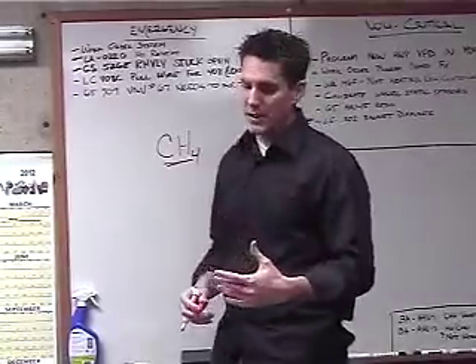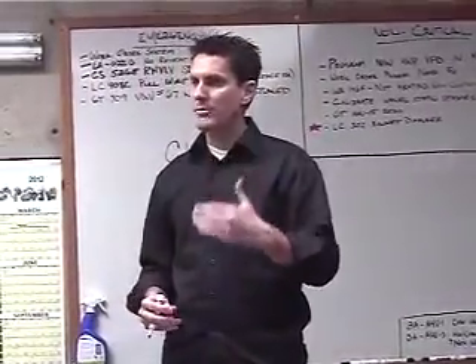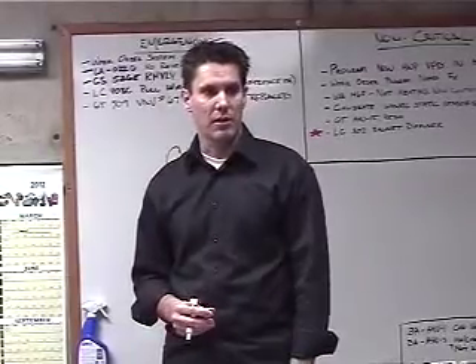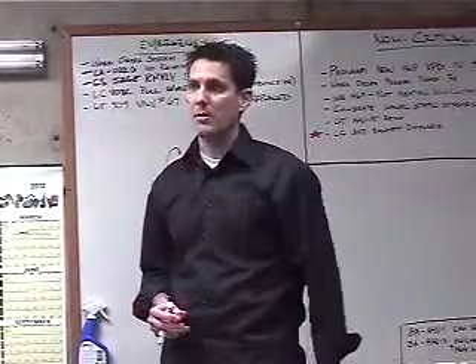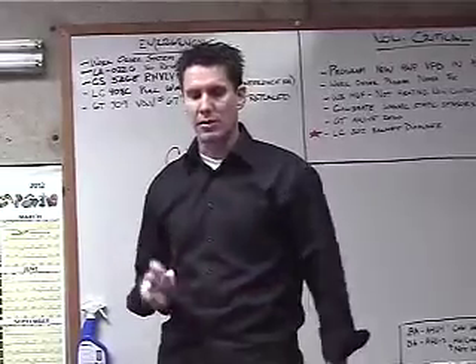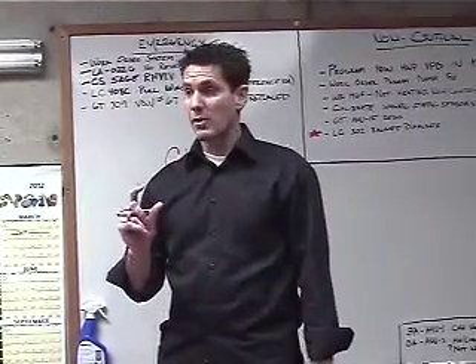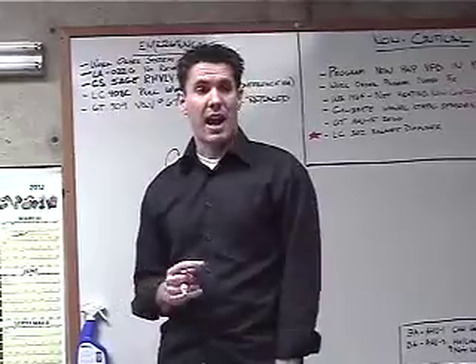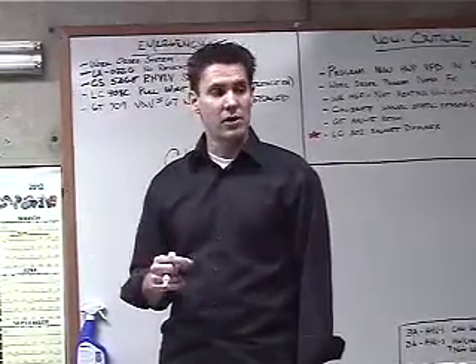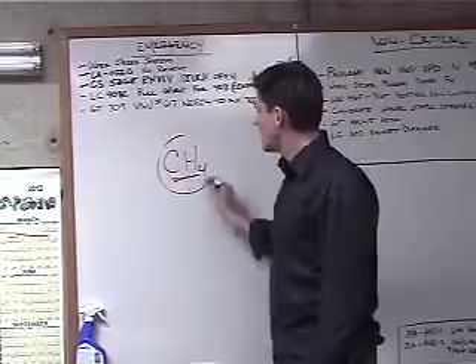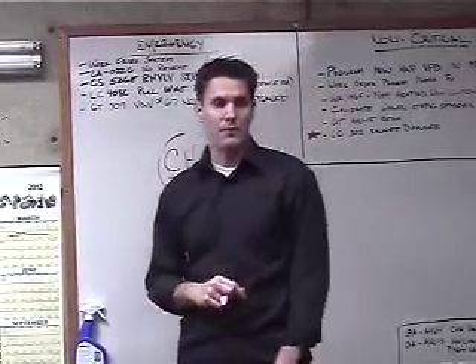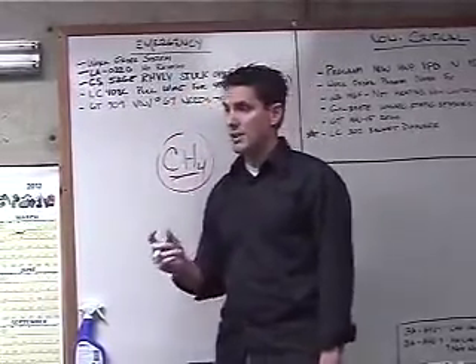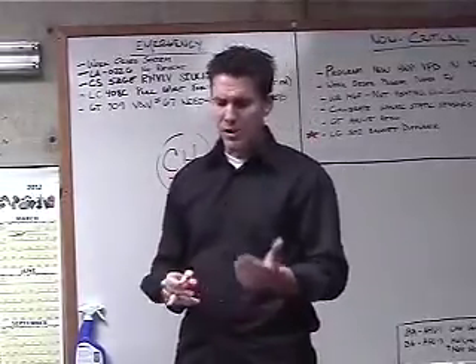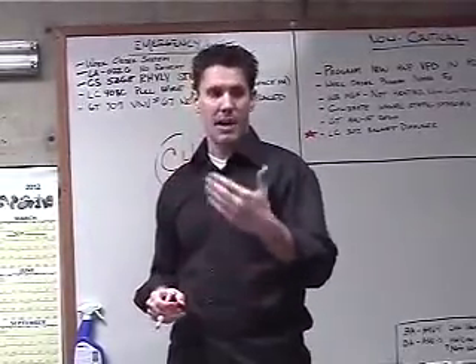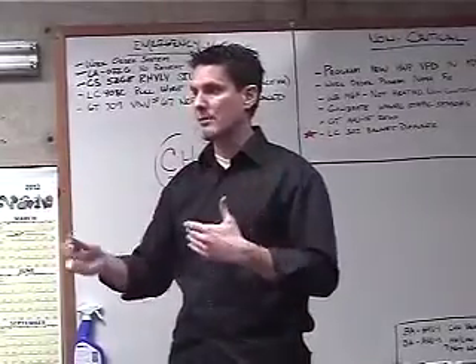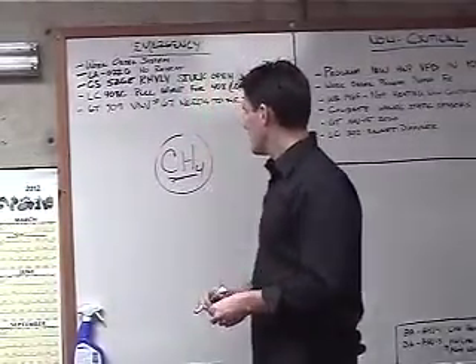The reason I say this is because as it changes, it's going to affect the way combustion is working inside of your boiler. When we started these boilers up, we went in and we calibrated these to the right combustion rate. But that was at the point of what the natural gas was at that time. So as it changes, as the CH4 percentage changes in the fuel, your combustion will change. We don't see a huge change there, but it does affect it. Where we see it being affected more is with the venting, with the piping on the exhaust side because of the air pressures. I'll talk a little bit about that in a second.